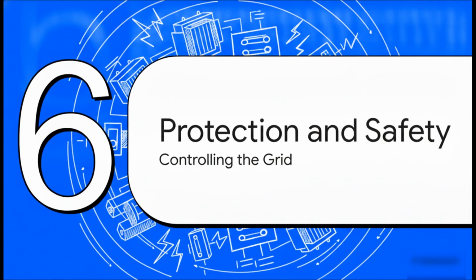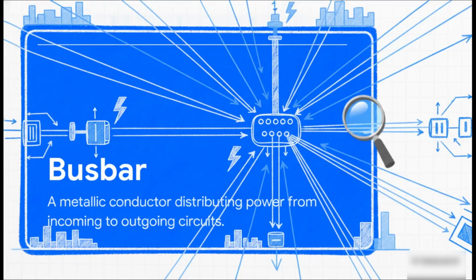Let's wrap things up with Part 6, Protection, Control, and Safety. All of these incredible components, the transformers, the breakers, the arresters, they all ultimately tie back to one core purpose: ensuring safe, reliable, and continuous power. And the physical place where everything connects is called the bus bar. Think of it as the grand central station of the substation. It's a thick, heavy metallic conductor, usually propped up by heavy-duty post insulators because of its sheer weight. The bus bar collects all the incoming power and perfectly distributes it to the outgoing circuits, constantly balancing the load so one part of the city doesn't get fried while another part goes dark.